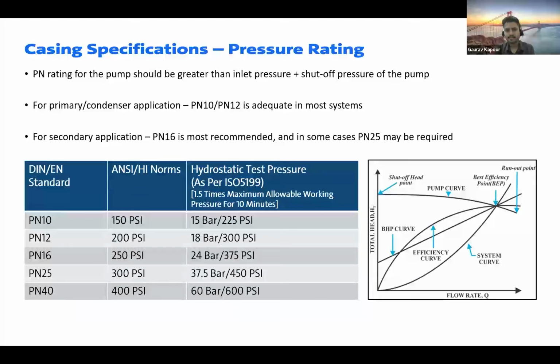Now if you look at casing specifications, it is very important to understand that depending upon the static height of your building on the suction side, your pump casing should be designed accordingly, for example PN10, PN16 or PN25, and tested as per ISO 5199 at 1.5 times the allowable working pressure for 10 minutes. It means if you're buying a PN10 pump, or if a PN16 pump is required at site, it should be tested at PN24 bar for 10 minutes as per ISO 5199.